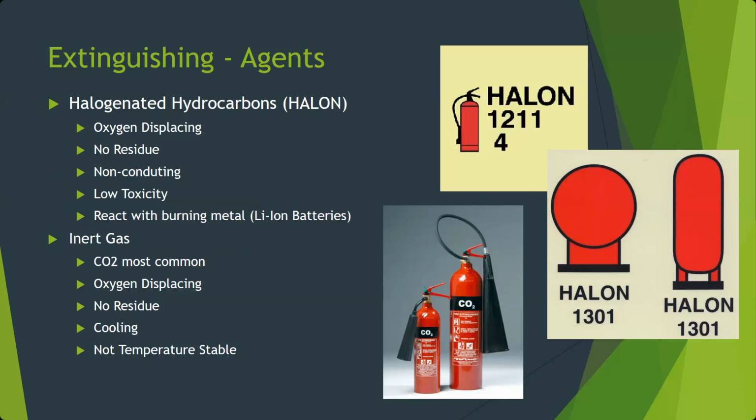It's probably not going to cause long-term health effects, but it has the chance to kill you right then and there if it gets rid of all the oxygen that's around. So low toxicity, but has the ability to hurt you because of the oxygen displacement. The other issue with halon, anyone know what the big issue is worldwide? They're an ozone depleting chemical, the various halons. And so a lot of these, they've stopped production of them. So most of the halon we use today is recovered and recycled when possible.